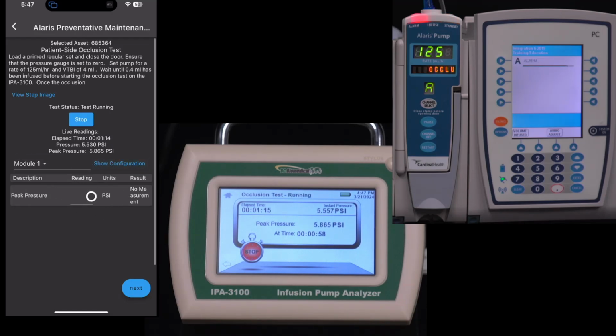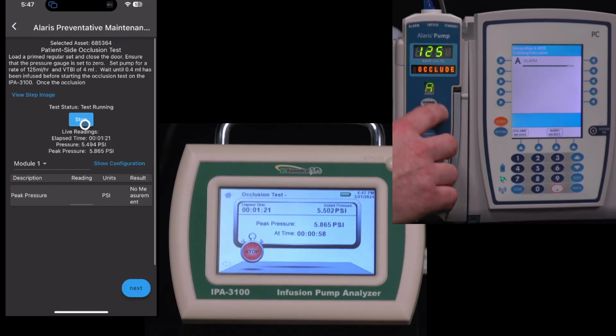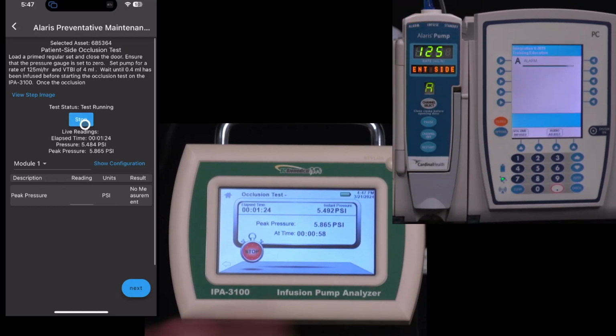Now, once I stop the test, it's going to then get that peak pressure. So now it detected the alarm, patient side occlusion, my favorite silence button, and I'll hit stop here. What that's going to do is end the test and read that value into MyBC Mobile. So that was our peak pressure. Now that failed, and it's telling me right here, you've got a failure in your test. Now, the service manual says that we should have a pressure around 7 psi. So our pressure is a little low here, so it's telling us that, yeah, we've got a failure in our test. So those test limits were built into the auto sequence, programmed in when we created the test sequence. And so it knows whether this data is good or bad.